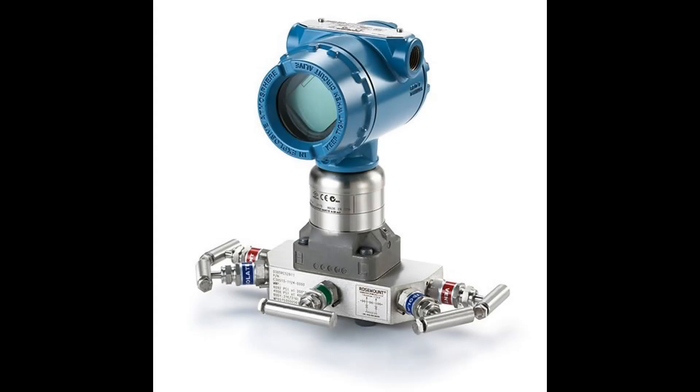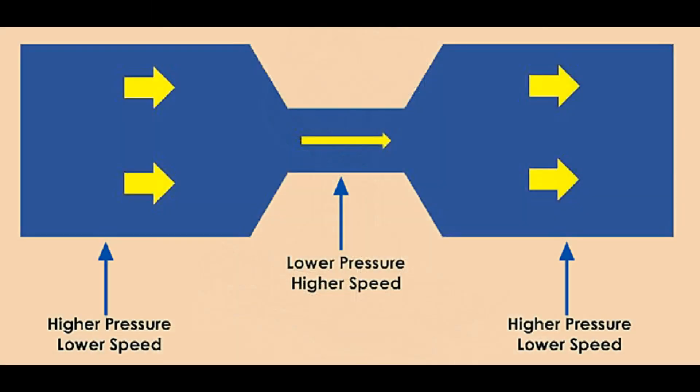A differential pressure transmitter is a common device used in process industries. It can be used to measure fluid flow. It operates based on the principle of Bernoulli's equation, which relates the pressure drop across a restriction in a pipe to the flow rate of the fluid.